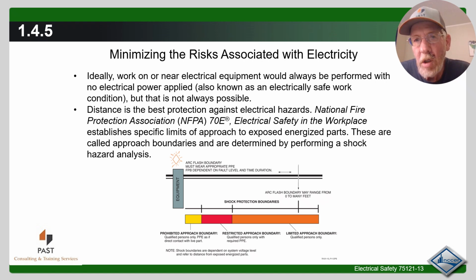Ideally, work on or near electrical equipment would always be performed with no electrical power applied. This is also known as an electrically safe work condition, but that is not always possible. Distance is the best protection against electrical hazards. The National Fire Protection Association, NFPA 70E, Electrical Safety in the Workplace, establishes specific limits of approach to exposed energized parts. These are called approach boundaries and are determined by performing a shock hazard analysis.